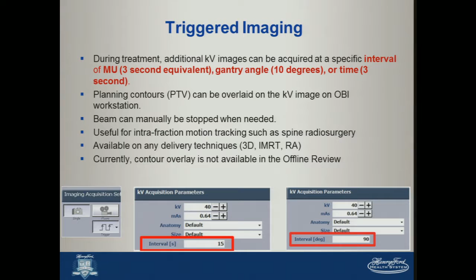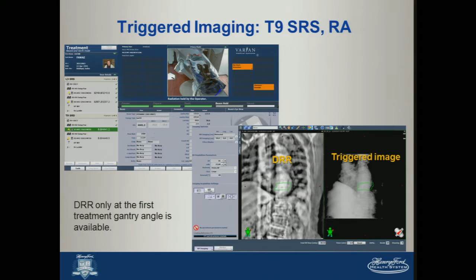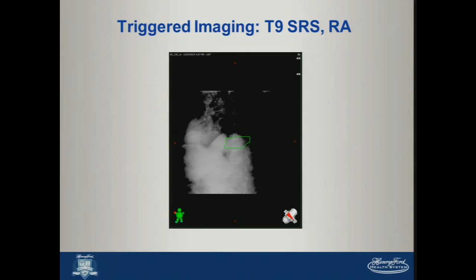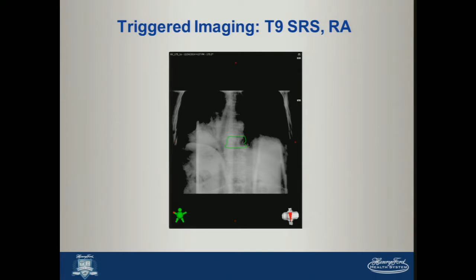So here's an example of triggered imaging. One of the current limitations, at least in TrueBeam 2.0, and I'm not sure whether it's been fixed in 2.5 or will be fixed in future, but the DRR is available only on the first treatment gantry angle. So at the console, the DRR becomes of limited use if you're away from that first treatment gantry angle. Nevertheless, you can superimpose structures such as the PTV on your images, which you kind of see here, to provide some assurance that you're treating the right target and still, patient's still aligned.